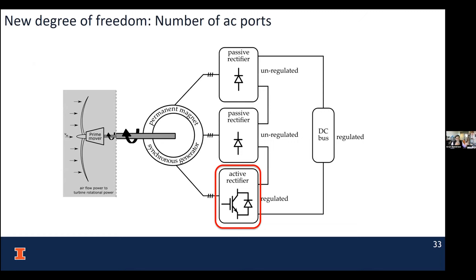Let's ask the first question: how much better can we do? Is it better than our conventional options? By doing this architecture, we have created a new degree of freedom in our design: the flexibility of picking how many ports we want. What we're showing here is a 3-port system, but I can easily construct a 4-port machine where 3 ports connect to passive rectifiers and 1 port connects to an active rectifier. So the number of ports, each 3-phase, is a degree of freedom in this design. Let's try to exploit that to reduce the active rectifier requirement.